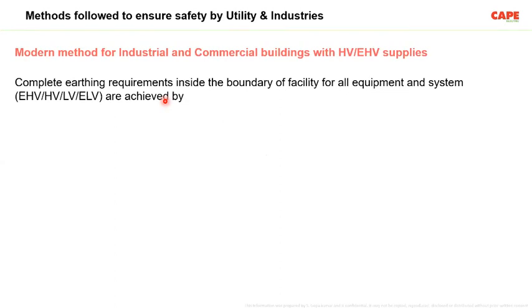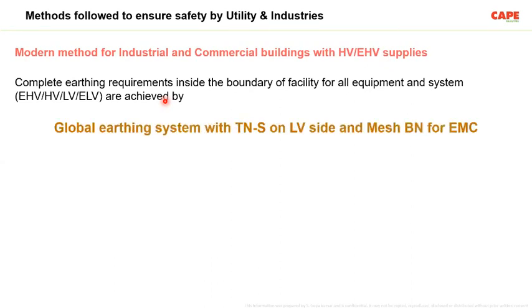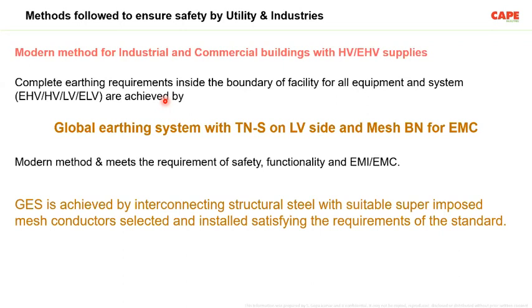But for modern industrial and commercial buildings with high voltage or extra high voltage supplies, the complete earthing arrangement can be made by a very modern method called the global earthing system. The name looks very fancy, but the advantage of the global earthing system is that literally no touch voltage exists. Two weeks back I was testing an installation with a 220 kV substation, 220/22 kV, and the 22 kV distribution goes to 8 buildings, and each building has 22 kV/400 volt transformers. Because this is a data center, they have a lot of load, I think about 75 megawatt.